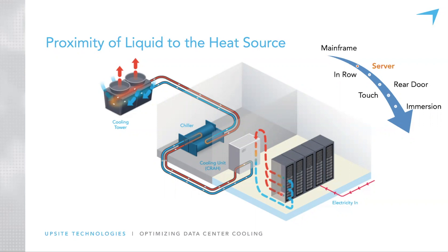With air cooling, air is the first loop — it picks up the heat from the source and carries it to a perimeter cooling unit, such as a CRAH unit with a chilled water loop or a CRAC air conditioner with a refrigerant cycle. The perimeter cooling units pick up the heat from the air, pass it into a liquid, and that liquid carries it away — either directly outdoors via a compressor-based system, or to a chiller and then to condenser water and out to the cooling tower.